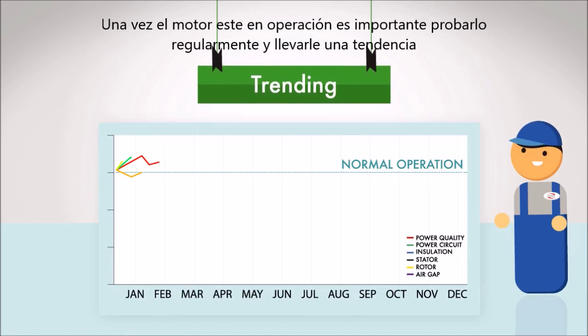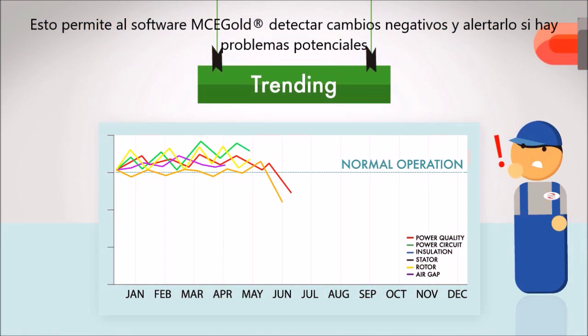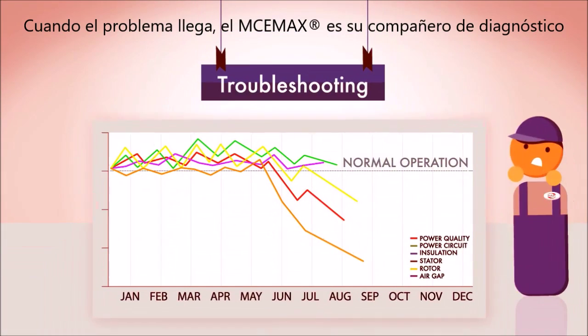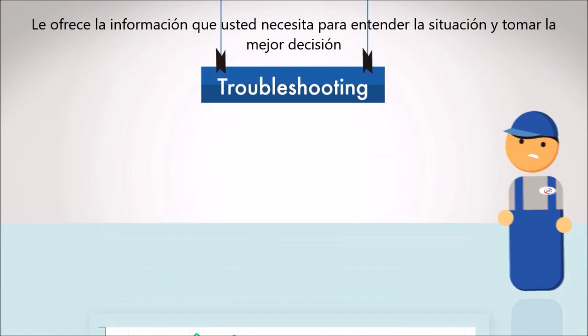Once the motor is operational, it's important to test it regularly to develop a trend. This allows the MCEGold software to detect negative changes and alert you of any potential problems. When problems do arise, the MCEMAX is your troubleshooting partner — it provides you with the comprehensive data you need to make the right decision.